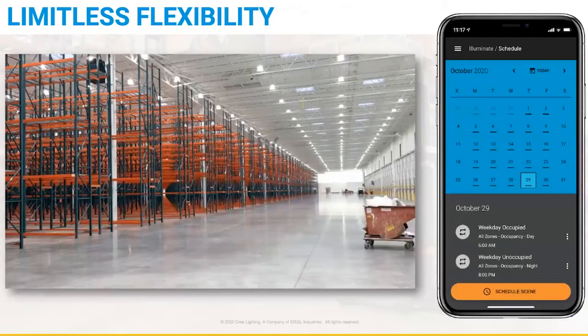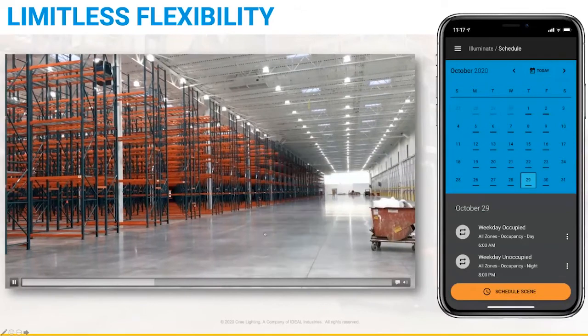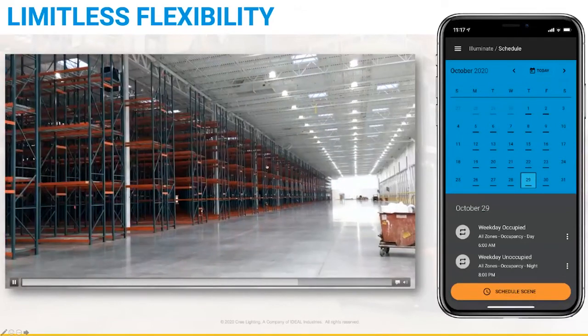Now, let's take a look at this in action. You'll see here, we've got a schedule set up, and there's 2 zones. So there's this scene, all zones occupancy day. That's set to run at 6 a.m. And then all zones occupancy night, that's set to run at 8 p.m. Now these use the same hold times and dimming levels I mentioned on the previous slide. So if there's no one around at night, the nighttime scene gets applied, and you can see all of those lights in the aisle shut off.